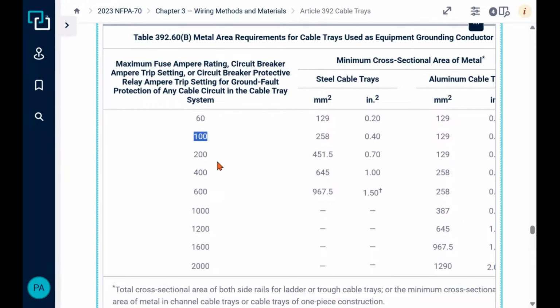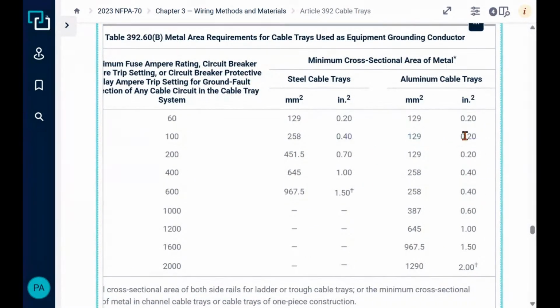So if you see right here, if it's 100 amp rated circuits, the maximum circuits in that tray are not going to exceed that. So you could have 60s in there, you could have 50s, 50 amp circuits, 75 amp circuits, whatever. Then you would go to the 100, and based on the steel, the minimum cross-sectional area has to be, for example, 100 would be 0.40 square inches, just like for the fill for a raceway, but this is what it would be here. So that's the minimum cross-sectional area for that. And then aluminum, same thing over here. This one would be 0.20.